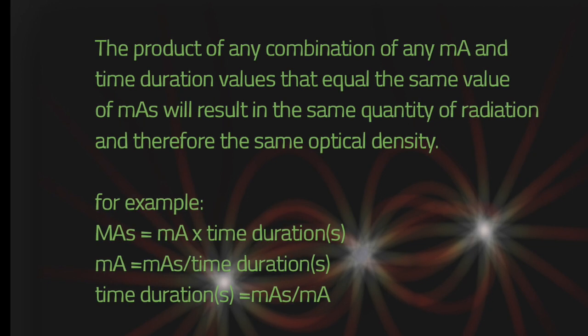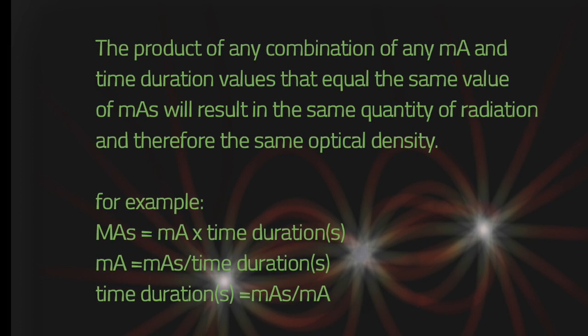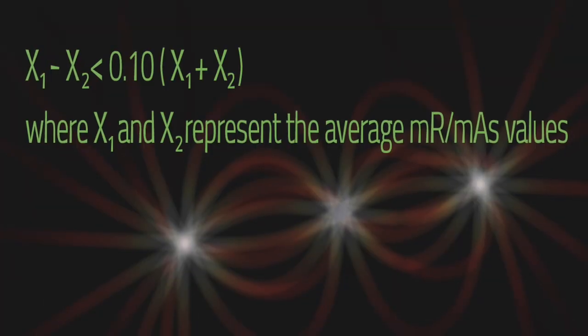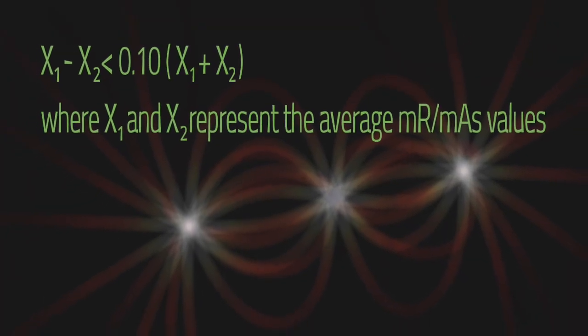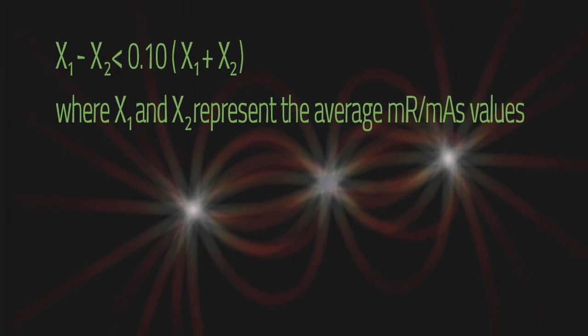In this way, linearity of mAs can then be tested using a computerized dosimeter, with exposure changing in mA and time proportions yielding milliroentgen per mAs measurements within 10% accuracy of one another. The following formula can be used to calculate the accepted level of linearity.